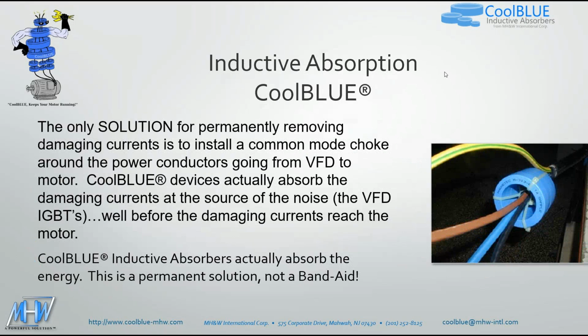The third solution is an inductive absorption device called CoolBLUE. The only solution for permanently removing the damaging current is to install a common mode choke around the power conductors going from the VFD to the motor. CoolBLUE devices actually absorb the damaging currents at the source of the noise, well before the damaging currents reach the motor. The CoolBLUE inductive absorbers take the energy and convert it into heat. This is a permanent solution and not a Band-Aid.